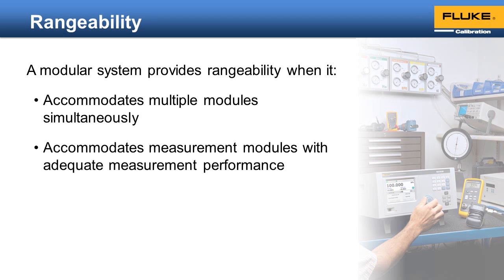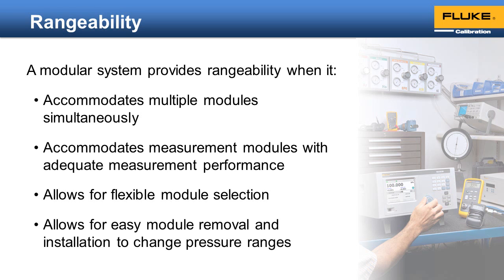And those modules need to be of adequate measurement performance to accomplish the required task. Also, the calibrator needs to allow for flexibility in the module selection. For example, if there are rules covering what the maximum ratio is between the highest pressure range and the lowest, then that eliminates the benefit of rangeability. And finally, to truly support the benefit of rangeability, the design must allow for easy removal and installation of modules to change the range of the system.